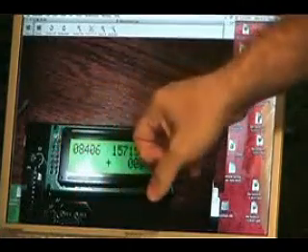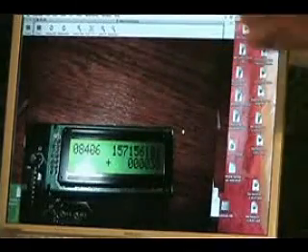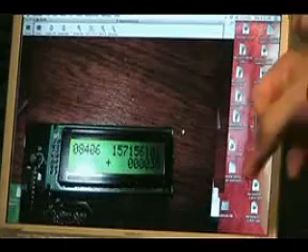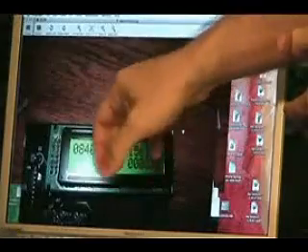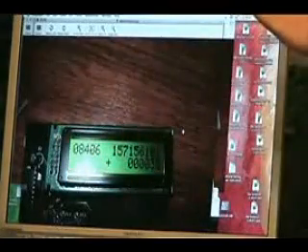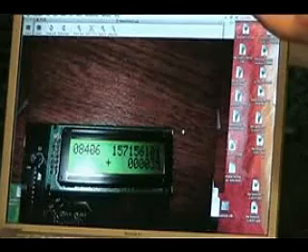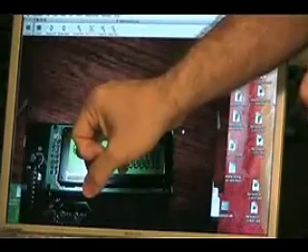Just like I said, my sensor displays the temperature. Remember I was saying it tells you if there's flow or no flow of a solution? Well, you see the temperature change differential. There are actually 2 thermals inside that sensor, and it sees the reference temperature and sees the difference of the heated one.